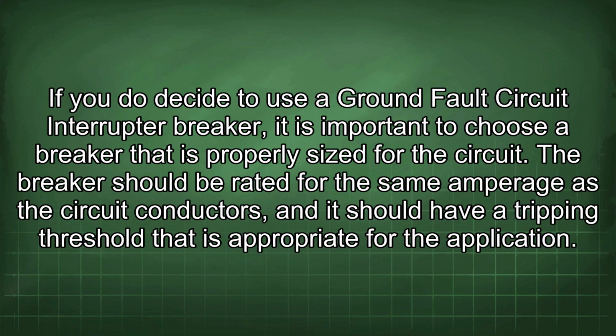If you do decide to use a ground fault circuit interrupter breaker, it is important to choose a breaker that is properly sized for the circuit. The breaker should be rated for the same amperage as the circuit conductors, and it should have a tripping threshold that is appropriate for the application.